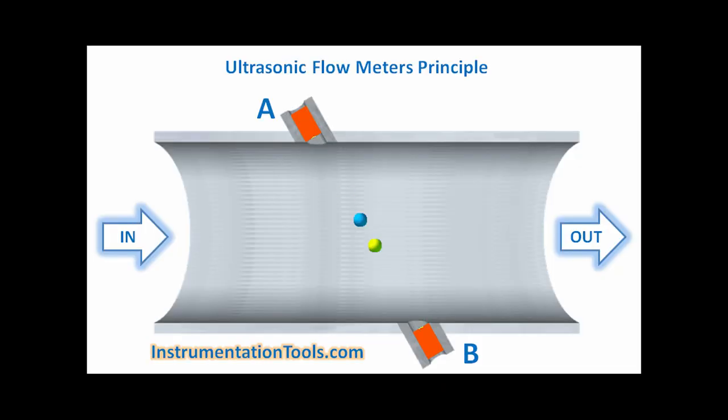As the liquid flows, the sensor angled with the direction of flow now transmits and receives in 0.8 of a second, while the sensor angled against the flow now takes 1.2 seconds.